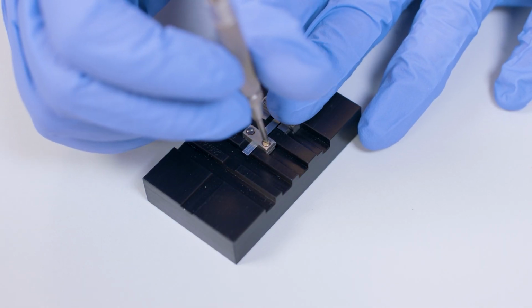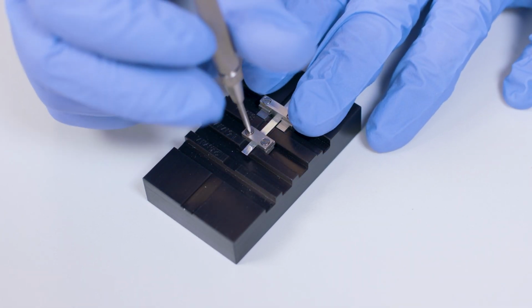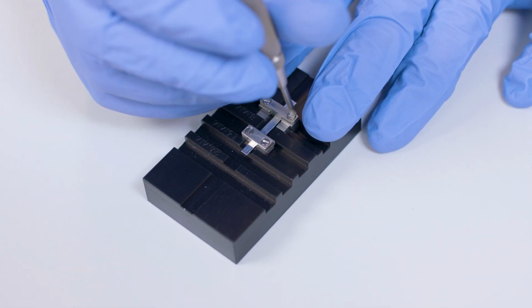The CTE calibration is based on a run in which a known material, such as aluminum foil, is heated at a constant rate and the dimension change is measured. For the CTE calibration, you can use aluminum foil and the film fiber clamp.